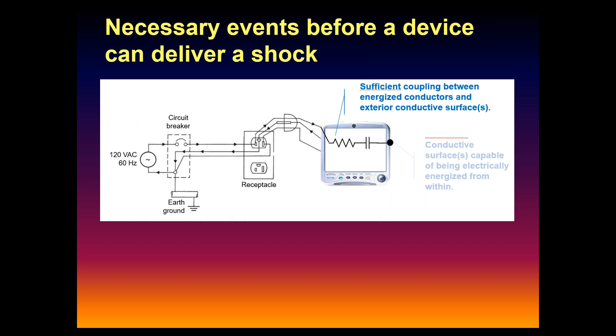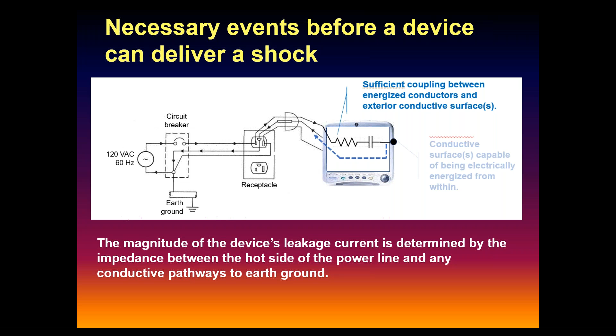First thing you've got to have for a shock: sufficient coupling between the live line and the case. There has to be sufficient capacitance and resistance before you have any meaningful amount of leakage current available to that case. That's the second thing. The magnitude of that leakage current is determined by the impedance, the virtual impedance inside the machine.